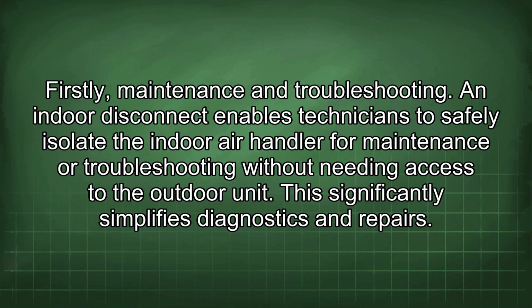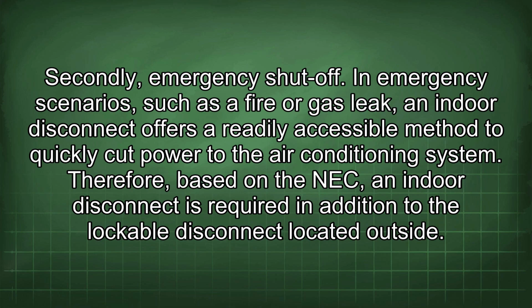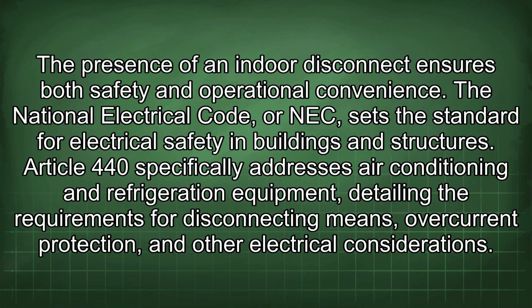Firstly, maintenance and troubleshooting. An indoor disconnect enables technicians to safely isolate the indoor air handler for maintenance or troubleshooting without needing access to the outdoor unit. This significantly simplifies diagnostics and repairs. Secondly, emergency shutoff. In emergency scenarios, such as a fire or gas leak, an indoor disconnect offers a readily accessible method to quickly cut power to the air conditioning system. Therefore, based on the NEC, an indoor disconnect is required in addition to the lockable disconnect located outside. The presence of an indoor disconnect ensures both safety and operational convenience.